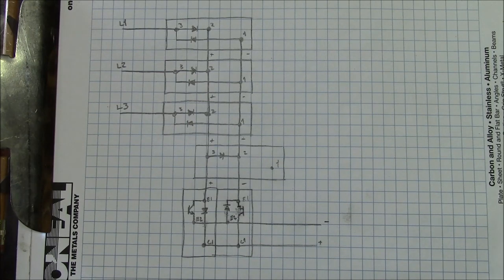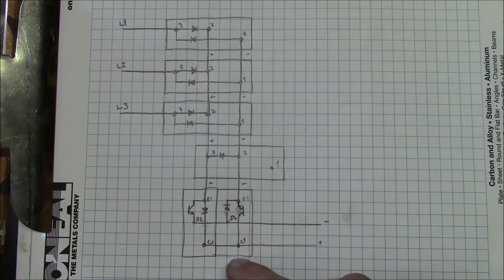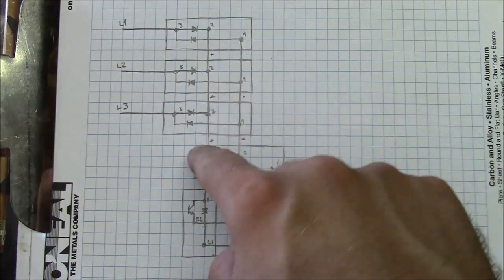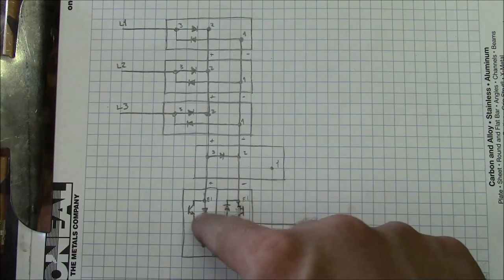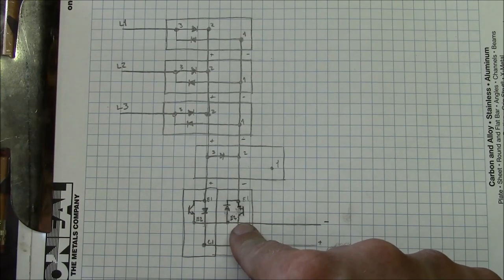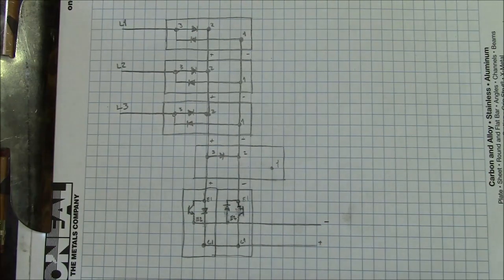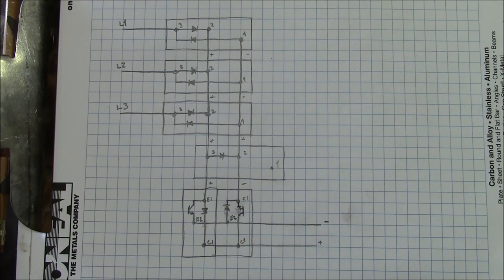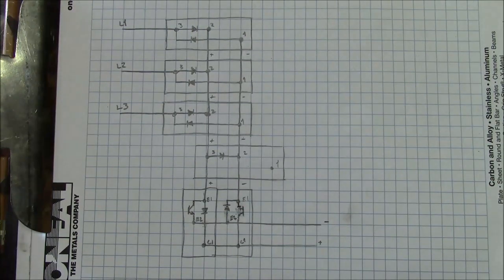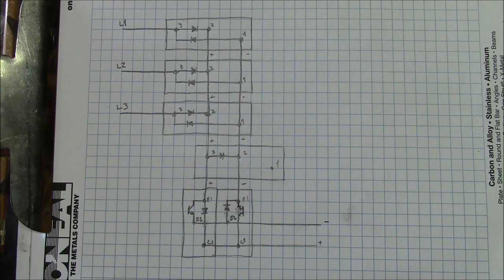I'm also not sure exactly how this FANUC power supply works. This is the schematic, and I've been trying to figure it out. This is super simplified, of course. But it rectifies the incoming AC three-phase power here into the DC bus, and then it goes through this other rectifier here for no known reason. And then it goes into these big power transistors right here. And as far as I can tell, the function of these power transistors is to reverse the DC bus. And there's no braking resistors at all. So I guess that it's a regenerative drive, and so it's dumping the current back into the grid. But I'm not sure how it accomplishes that from this circuit. So if anybody knows, I would love to find out more information about that.